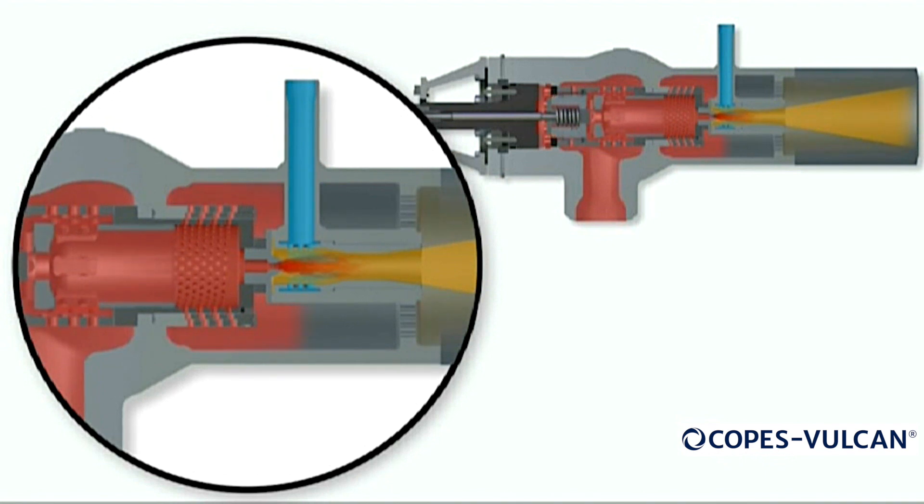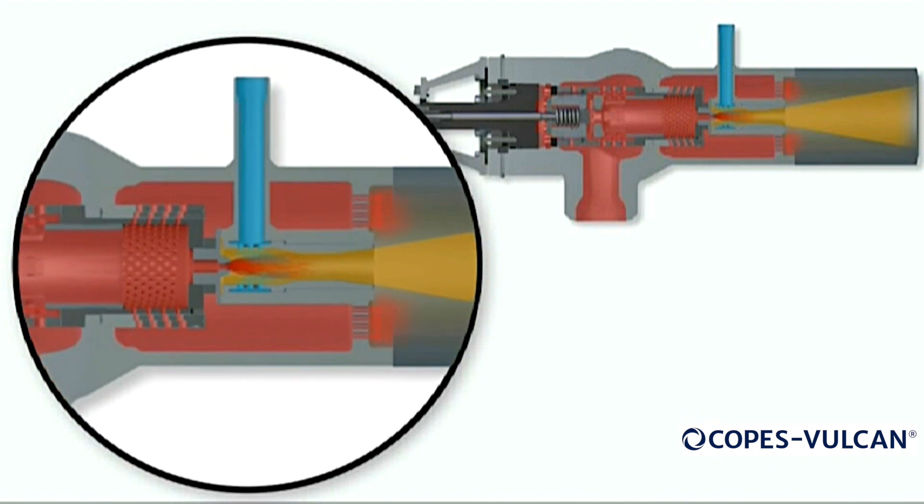As the cooling water is finely atomized and preheated, the final desuperheating takes place directly after the outlet diffuser section. With the outlet diffuser aligning the main steam flow to create an excellent mixing zone, the final stage of desuperheating occurs rapidly and evenly without danger of thermal shock or water dropout in the downstream pipework.